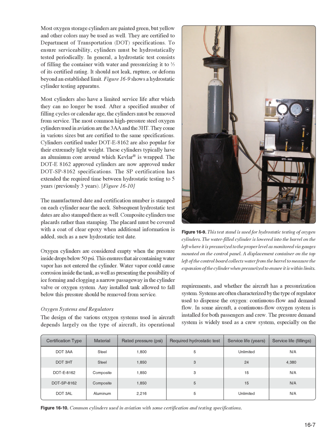To ensure serviceability, cylinders must be hydrostatically tested periodically. In general, a hydrostatic test consists of filling the container with water and pressurizing it to 5/3 of its certified rating. It should not leak, rupture, or deform beyond an established limit. Figure 16.9 shows a hydrostatic cylinder testing apparatus. Most cylinders also have a limited service life after which they can no longer be used. After a specified number of filling cycles or calendar age, the cylinders must be removed from service.